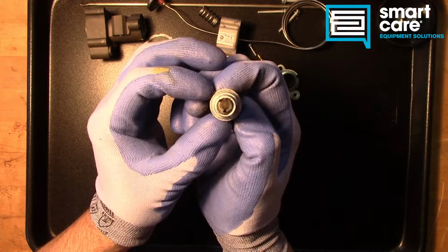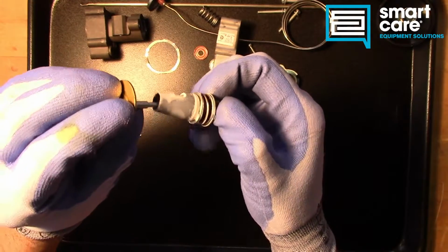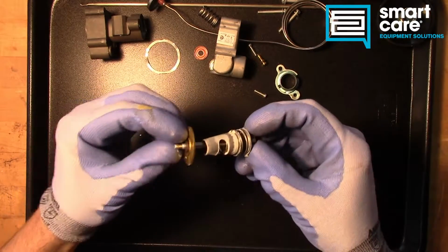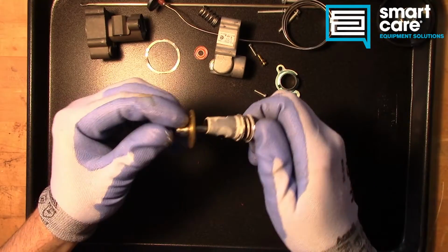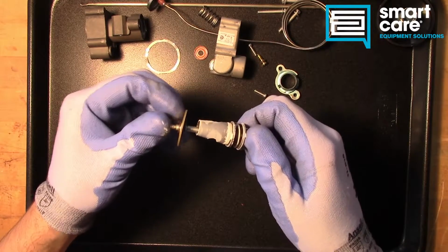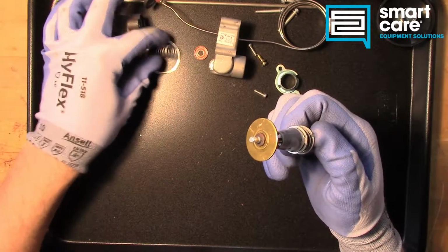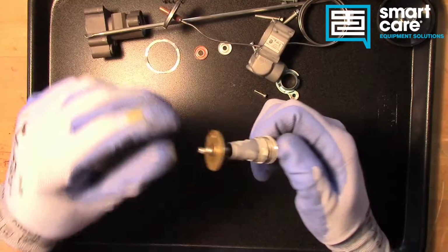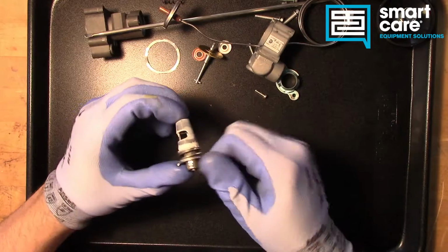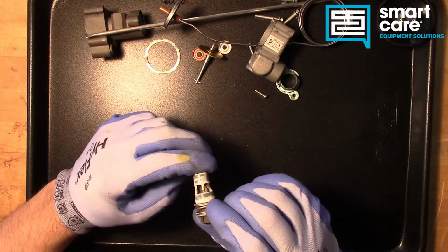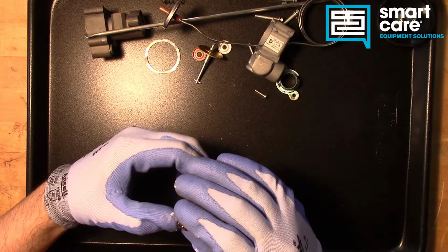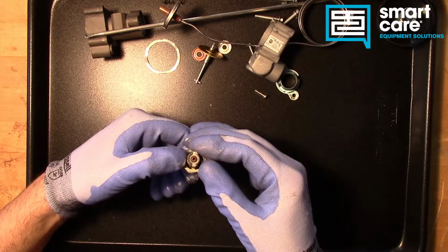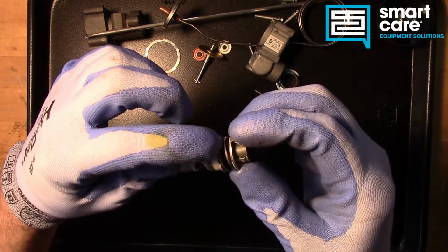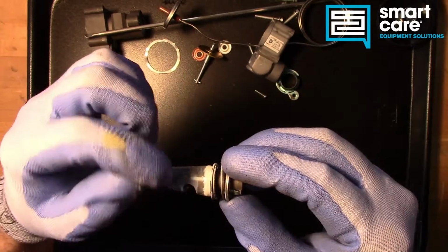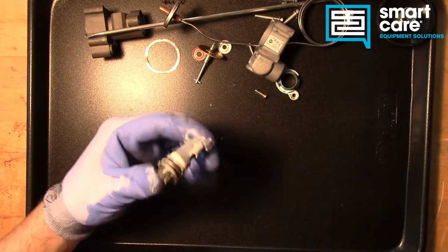Now in this, now you can see that T-slot down inside that this piece of the valve mechanism would slot into. So if you remember, we had this part threaded back here, and as we turned this, it's actually threading and unthreading this back in the back of the valve and changing the balance of the spring pressure against the bellows pressure. So let's take a look at how that calibration screw is set up in there. So looking at the way this goes together, looks like this spring is just on here to keep pressure against the valve seat, against the tapered part of the valve body, so it keeps it sealed. So let's just try and pop that off.